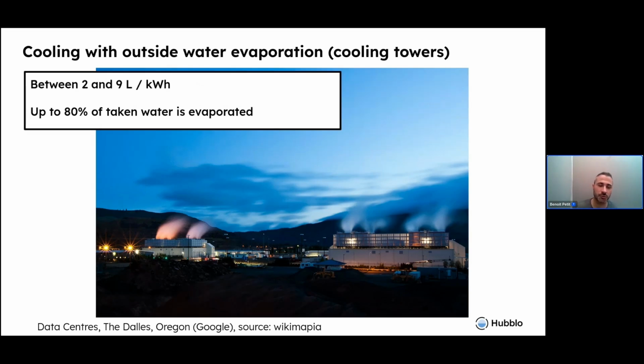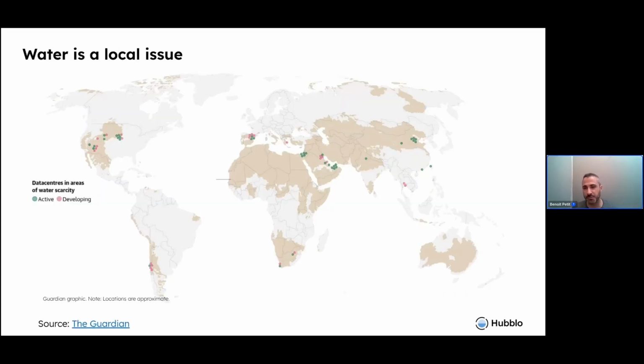And when we do water consumption assessment, we make the difference between taken water and consumed water. So basically, the water is consumed when it's evaporated. If it's a closed circuit and the water is sent back to the local environment, it's not considered consumed. But here, with that kind of system, it's up to 80% of taken water that's evaporated. This technology basically is a disaster when the local area knows water stress already. And that's why you might have seen in the media many news titles about AI consuming a lot of water coming from data centers that use that kind of technology. So the thing about it is that it's a local issue. Building a water intensive data center in the desert of Nevada doesn't have the same impact as building it in an area that doesn't have significant water stress. And the thing is, a lot of data centers are built in those stressed areas. And we will see one in a few slides.